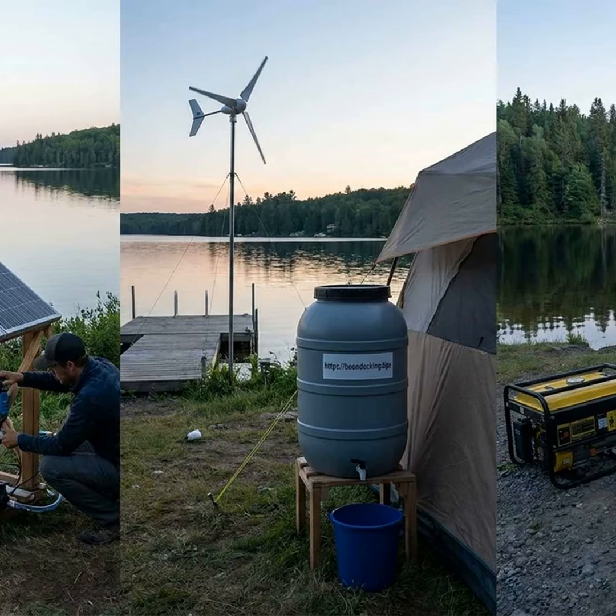Assess climate and resources. Note sun hours, wind patterns, water availability, flora-fauna issues. Estimate loads. Calculate daily kilowatt hours and water use per person, e.g., 150 to 250 liters per person, including basic household needs. Include any gardening or livestock. Choose generation mix. Allocate solar, PV capacity using local sun data, plus consider wind or hydro if available. Ensure PV can recharge batteries from empty in one average sunny day.